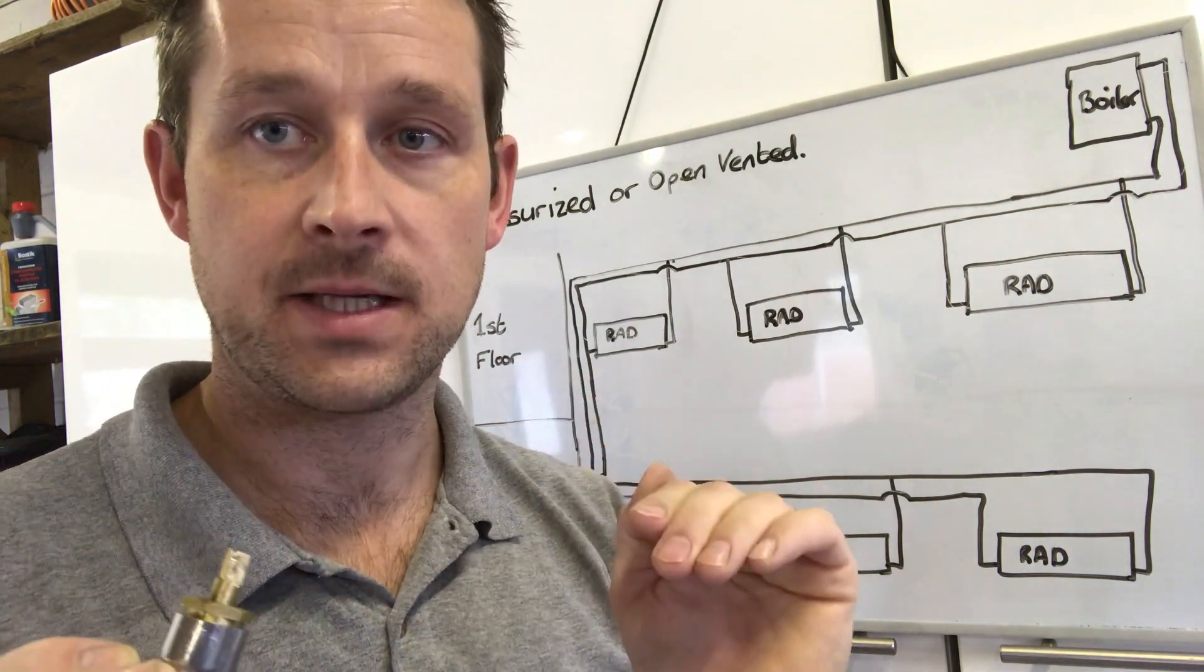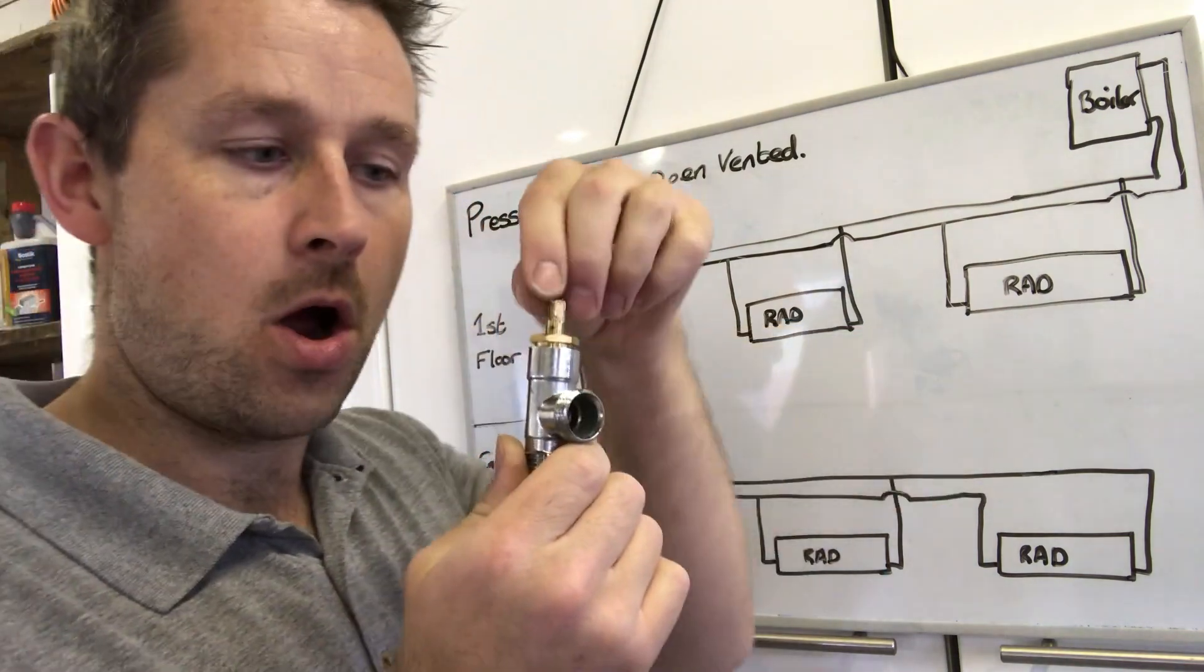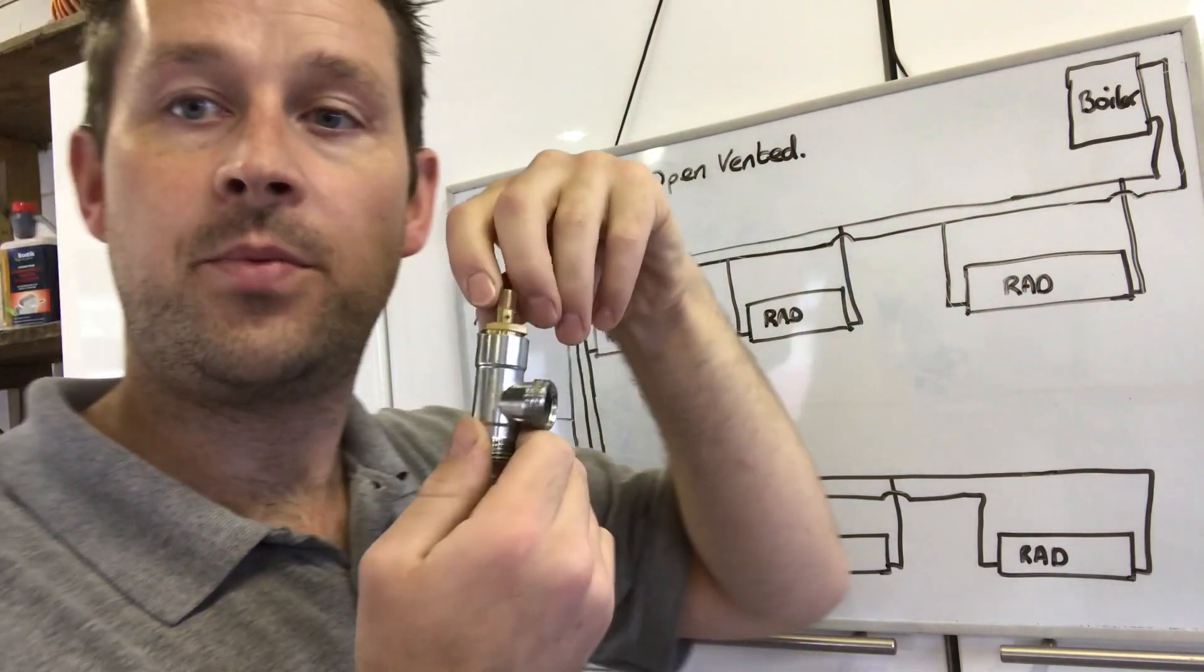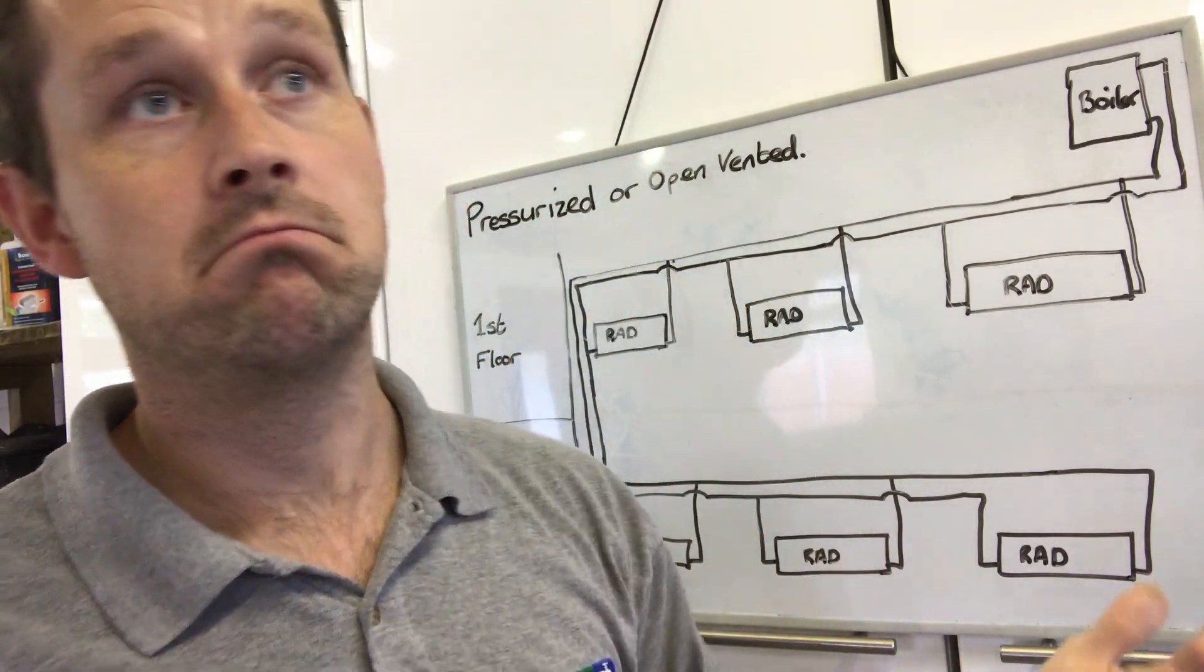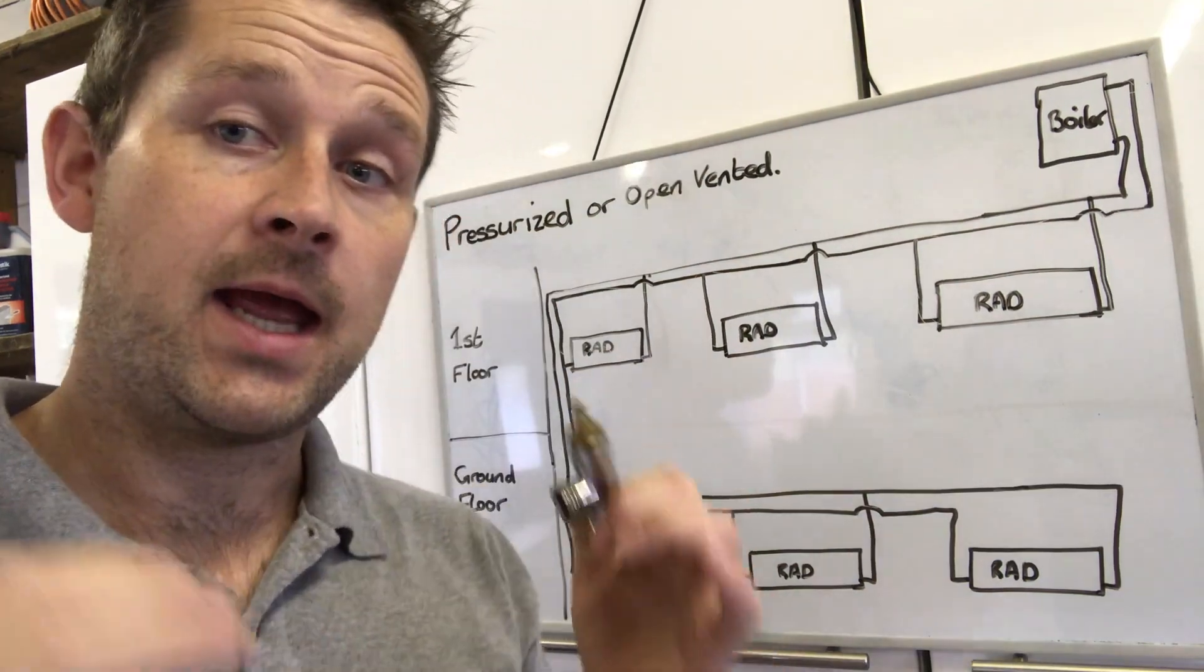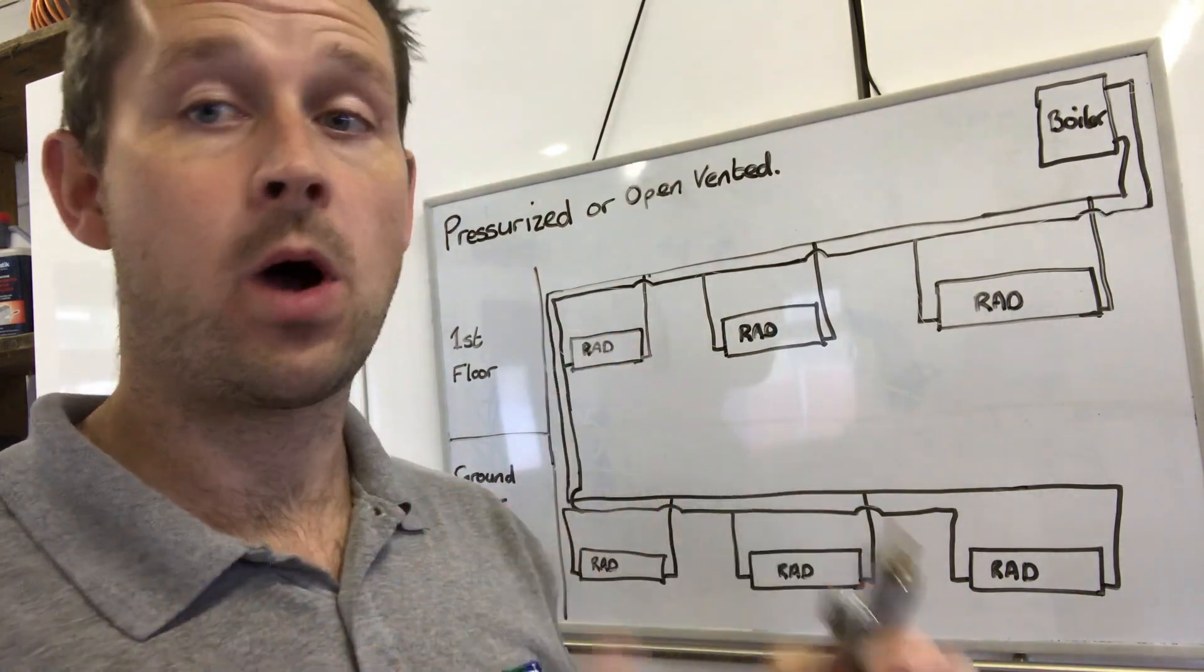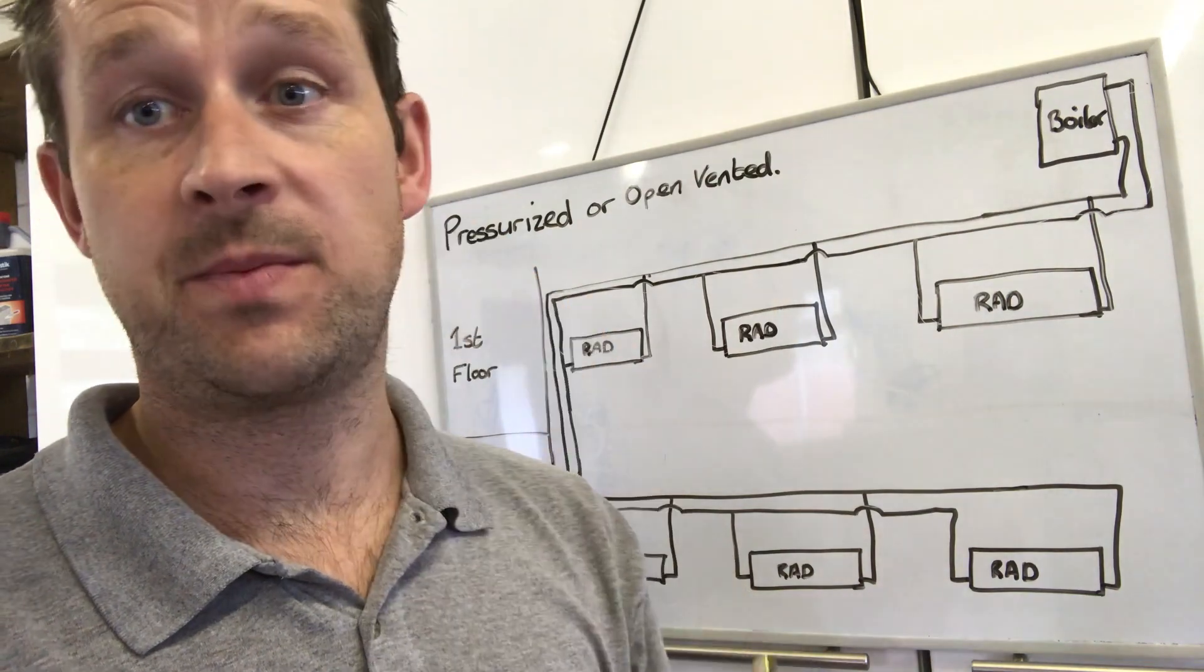That is generally the basic starting point. So just to recap on that, downstairs open one turn, upstairs open it one and a half turns, and you'll find that 90% of the time solves all the issues. That in a nutshell is generally how we balance the radiator system and why we balance the radiator system.